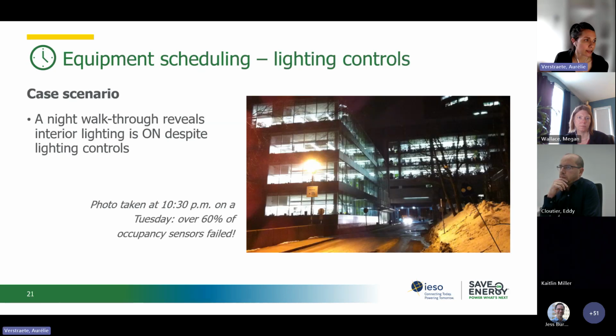Then the last example for scheduling opportunities is for lighting. Here we have a building, and a night walkthrough reveals that the interior lighting is on despite lighting controls. Then the investigation revealed that the majority of occupancy sensors are faulty. So everyone thought that the lights were off during the night, but they were not.